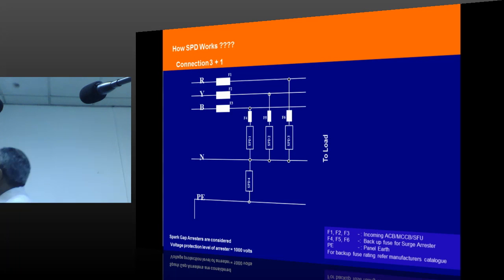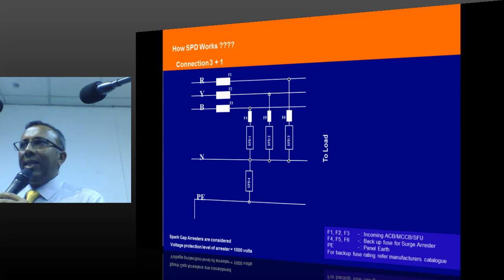You imagine there it's a 3-phase 4-wire network, R, Y, B phase, neutral and the earth line. You imagine that this is a distribution board, incoming and finally it goes to load. I am just trying to explain how SPD works. You imagine that there is a lightning strike and the ground potential is increasing. A lightning strike on the building, ground potential increases. That means this PE wire is going to have high potential with respect to the service incoming. Because this service is connected to a transformer maybe far away. So with respect to a service which is connected far away, we are going to have a high potential at the PE conductor. And you imagine 4 SPDs are connected, SPD 1, 2, 3, 4.